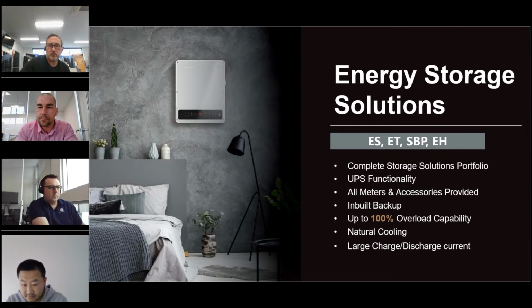So with a single phase hybrid, you need a meter and you need a CT. With a 3-phase hybrid, you need a 3-phase meter and 3 CTs. We include this in the box free of charge, installer. Our backup's inbuilt, so there's no external backup device at an extra cost that you have to pay for.